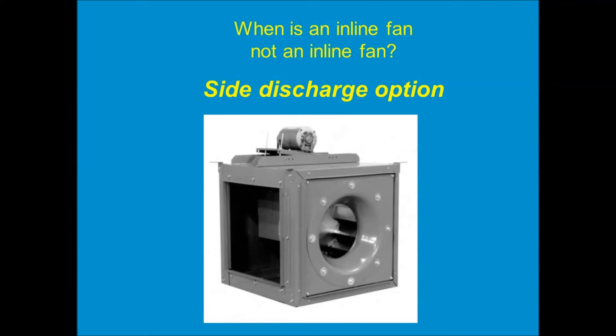Here's a little pop quiz: when is an inline fan not an inline fan? Well, it's when we use the side discharge option. This square inline fan is really just a pressurized plenum — that little centrifugal impeller is like a plug fan, just drawing air in and pressurizing the box. The air will leave whichever way is the path of least resistance. Most of the time the back of the fan is open so air comes in one side and leaves the other inline, but if we put a panel on the back and open up one of the sides with a duct collar, the air will turn 90 degrees and shoot off the fan from the side — with no loss of performance.